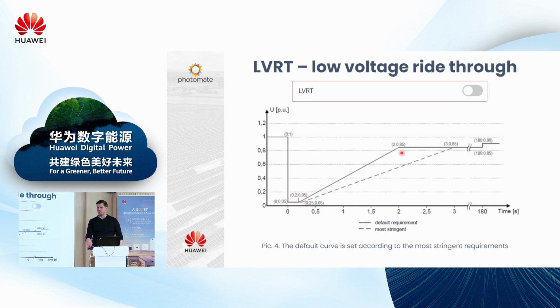Example where you can use it: if you have some industrial area, guys welding all the time in the neighborhood, and you have very unstable voltage in the grid. This function allows the inverter to keep working instead of turning on and off again, because that takes time, and this procedure will repeat over and over again, and you are losing the power you could generate in this time.